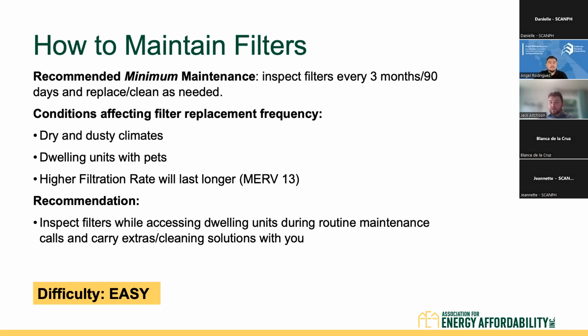And then a higher filtration rate will actually last longer. That's a bit of a misconception, that if you have a higher filtration rate, it should get clogged earlier. That is not the case. Essentially, a higher filtration rate is a thicker filter, and that allows for more filtration for longer. A recommendation here is to inspect filters while accessing dwelling units during routine maintenance calls and carry extra filters as well as cleaning solutions with you. There are two types of filters out there. There are one-time use filters, and there are also filters that can just be cleaned with a soapy water solution.